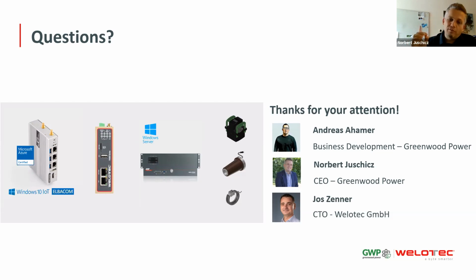What all these devices have in common is that they could or should understand the IEC standard. If they look at the standard and see they need 2 megaohm, 50 picofarad input impedance for the sensors to work, plus 3.25 volt level for voltage sensors and 225 millivolt for current sensors—there aren't many parameters. IED manufacturers can easily adapt to these, making them immediately compatible with Greenwood Power products, or even our competitors'.